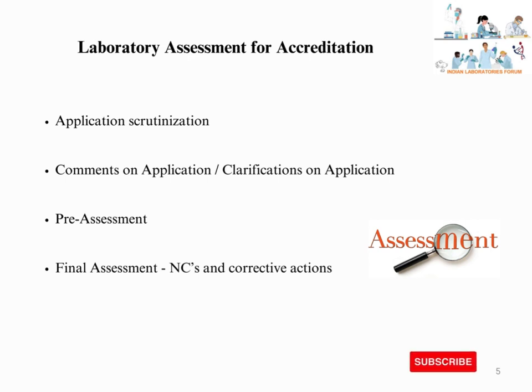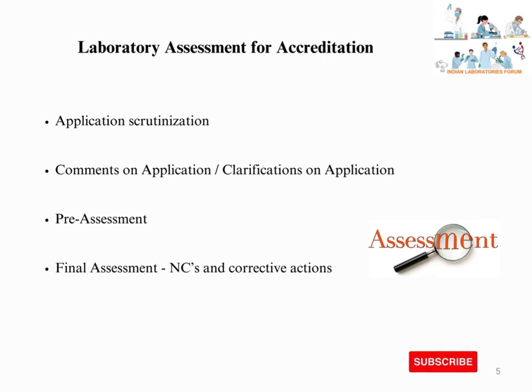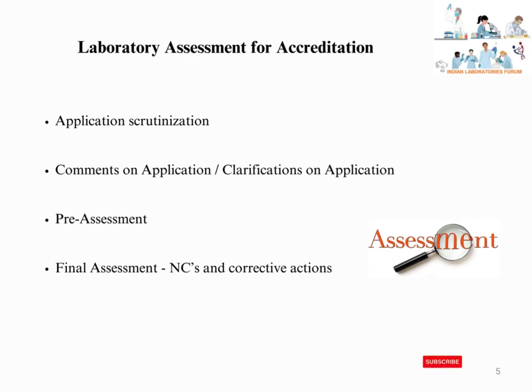The laboratory has to close those pre-assessment observations before proceeding with the final assessment. Upon closure, the accreditation body allots an auditor for quality manual adequacy review. The auditor reviews the quality manual and provides comments or observations, and the laboratory must correct the quality manual accordingly. Upon completion of quality manual adequacy, the accreditation body schedules the final assessment and assigns auditors — the number of auditors depends on the scope of testing submitted by the laboratory.